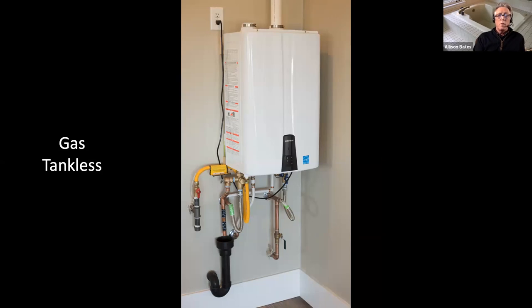As you know, with the standard gas water heater, like the first one I showed, the natural draft gas water heater, if you put your hand on that flue when it's firing, it's going to be very hot and you'll burn your hand. So there's a lot of heat going up in the exhaust gases. You can capture that heat by condensing the water vapor in the exhaust gases with the secondary heat exchanger, and that's called a condensing water heater.